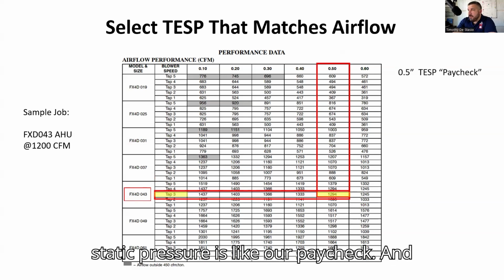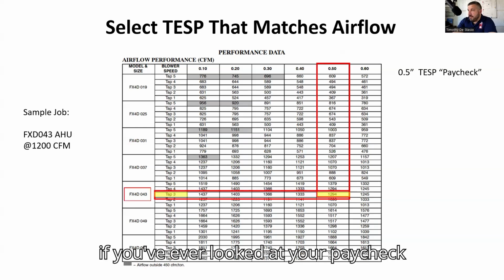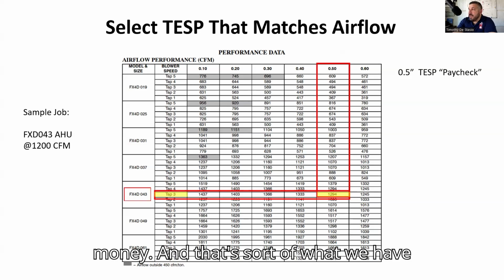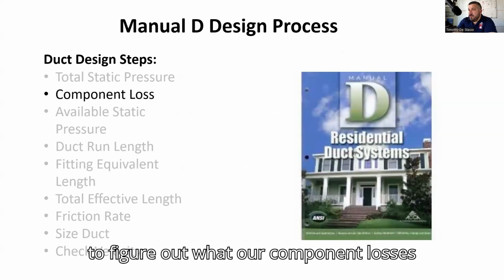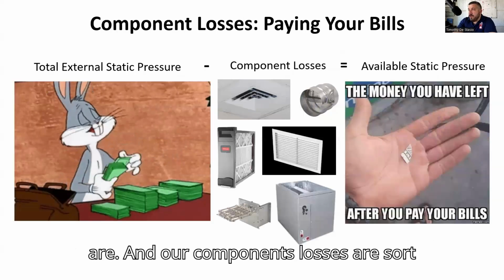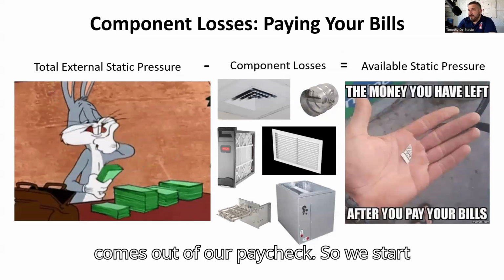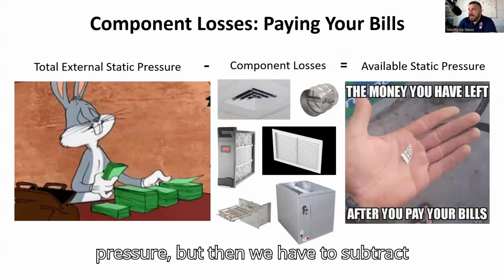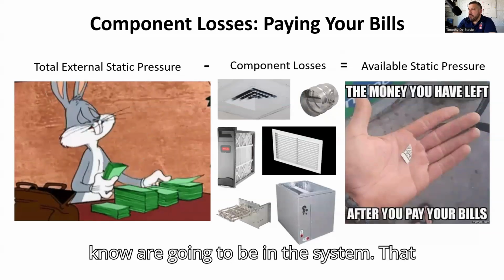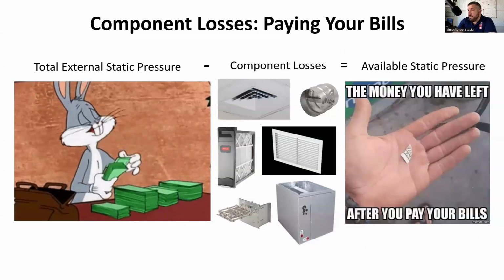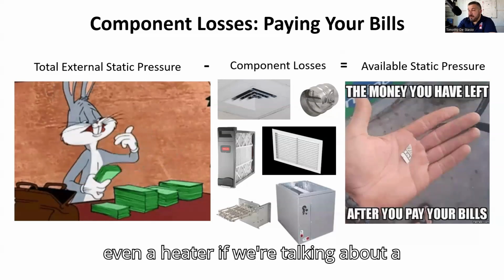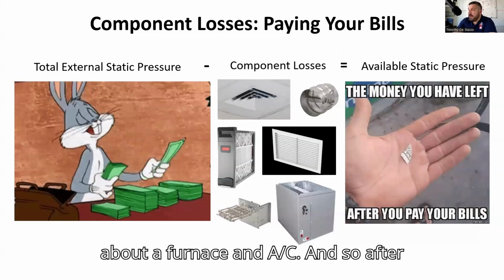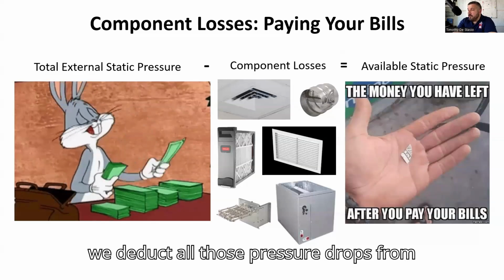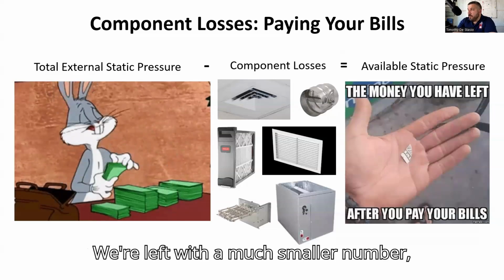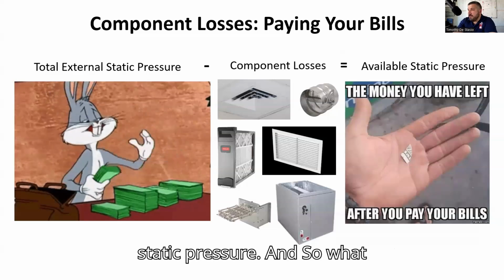So we want to think about that starting static pressure as like our paycheck. And if you've ever looked at your paycheck before everything starts coming out of it, it looks like you've made a lot of money. And that's sort of what we have when we start out with 0.5 inches static pressure. But the next step is to figure out what our component losses are. And our component losses are sort of like taxes and everything else that comes out of our paycheck. So we start out with a total external static pressure, but then we have to subtract the pressure drop of the things that we know are going to be in the system. That can include a supply register, a damper, a media filter, a return grill, even a heater if we're talking about a heat pump, or a case coil if we're talking about a furnace and AC. And so after we deduct all those pressure drops from that total external static pressure, we're left with a much smaller number, and that is what we call our available static pressure.